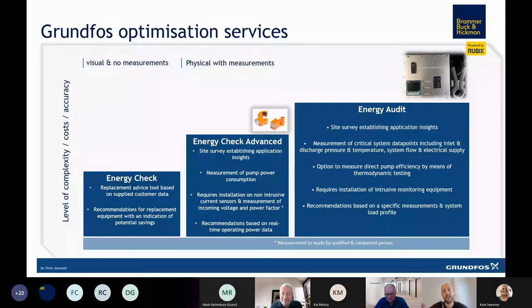This is where we gather great information, including about motor size. If we measure a pump of a certain kilowatt rating but it's going nowhere near that load, is there any need to put in a like-for-like replacement? Can we look at the curve of the existing pump and see what duty point it's actually running at? We have a conversation, and if that matches the site's usage without causing problems, why not offer a smaller alternative? As mentioned elsewhere, spares become cheaper too, since you're not using a bigger pump than the system requires. This is all based on real-life operating power data.